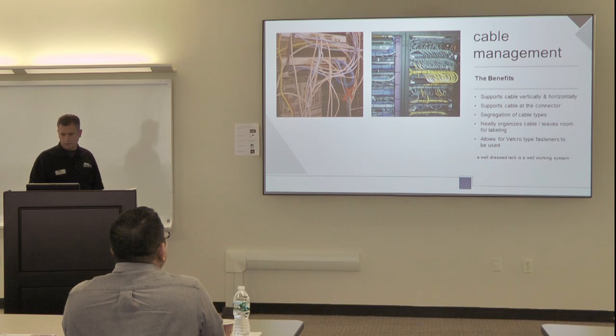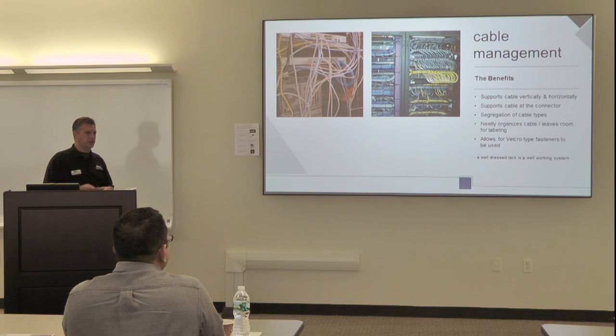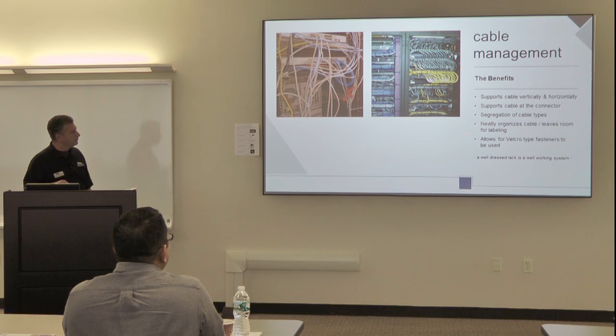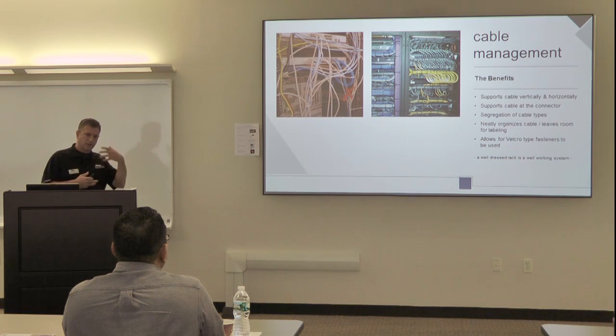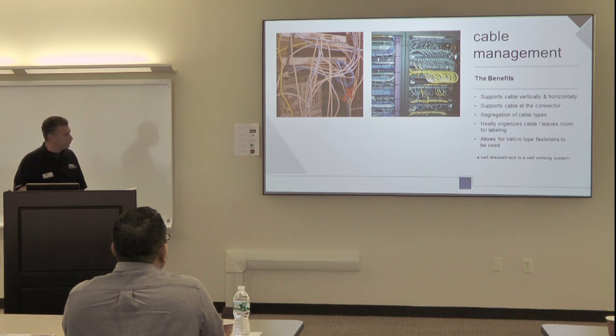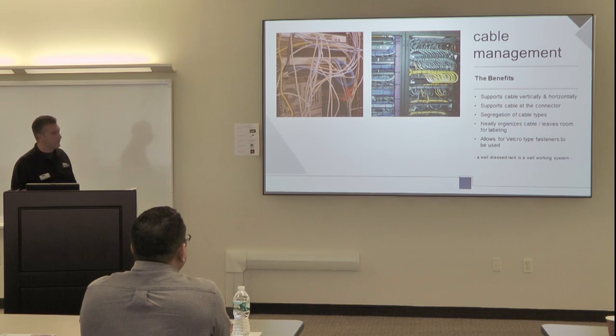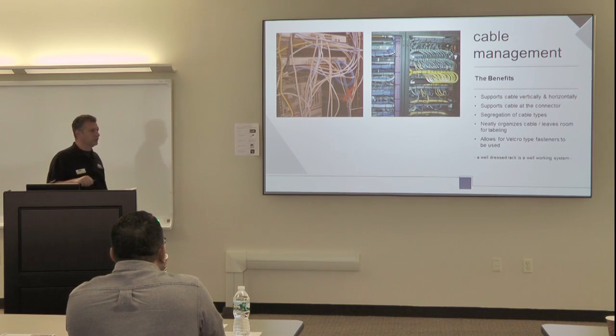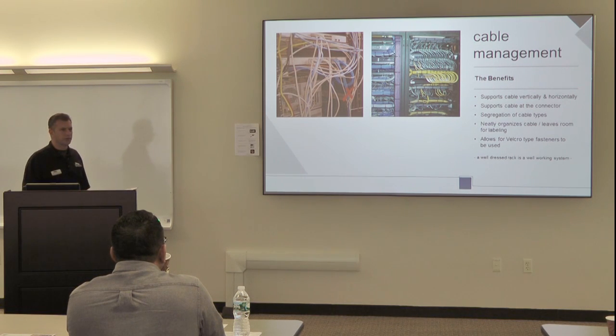So the benefits we touched on a bit: supporting the cable basically takes the strain off the connection. Segregation of cables helps with finding things, and keeps power and signal cords from being too close together, which you don't want. Vertical lacing gives you a good way to segregate cables and keeps things neat. A lot of the vertical and horizontal hardware out there now uses slots instead of holes, for Velcro, as you move away from wire ties—especially with category cable, where you shouldn't use wire ties because of over-tightening. A well-dressed rack is a lot easier to work on and leaves a great impression for you and your company with the end user or customer, instead of having something like this.